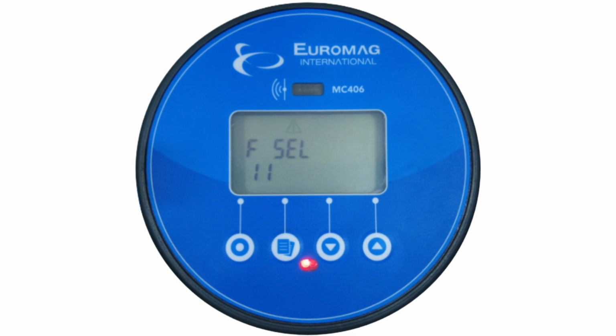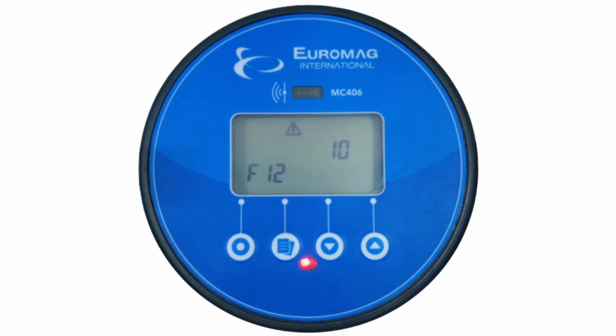Next we will need to set function number 11. This is the time and date which will be time stamped on the data logs and graphs. Function number 12 is damping, or the number of samples averaged to calculate the real-time value displayed. A higher value will average more samples, resulting in less fluctuation from one reading to the next.